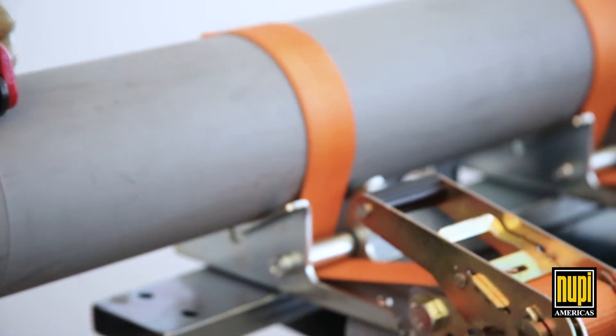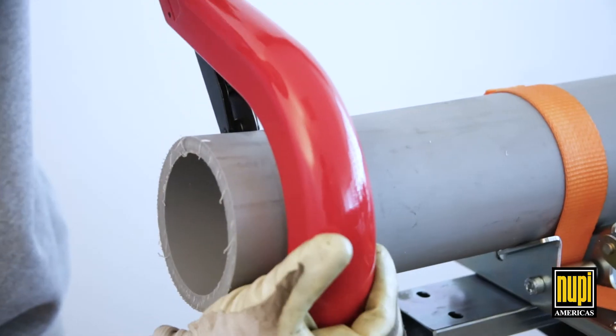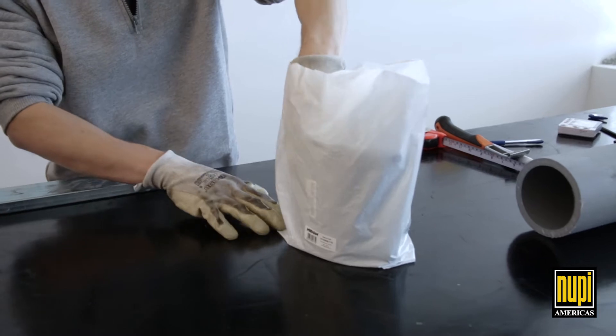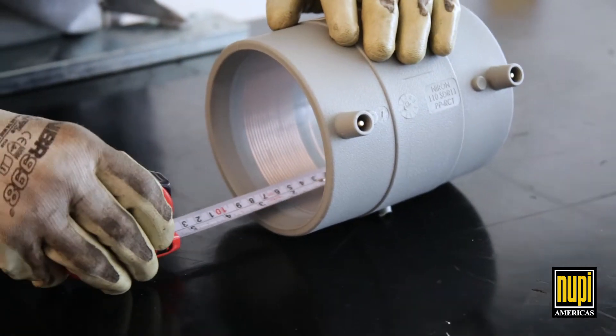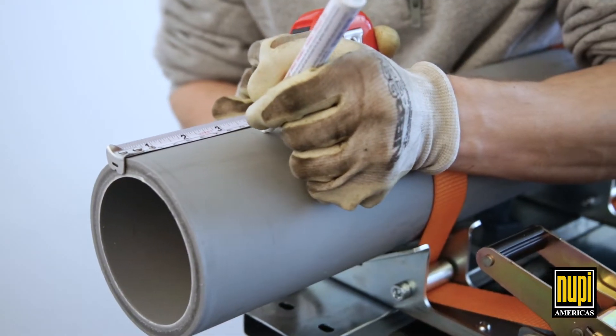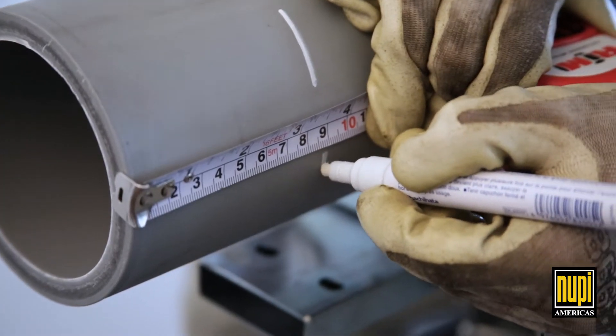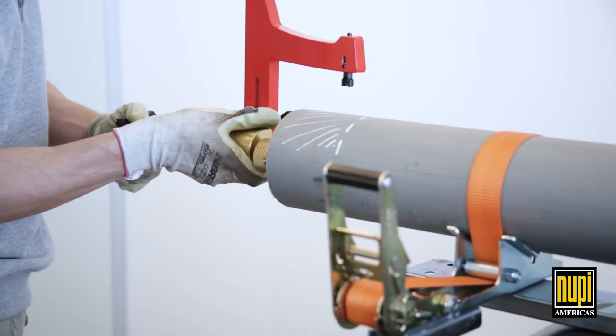Cut the pipes at right angles with a pipe cutter. Scrape the pipe and the fitting spigot surface uniformly to completely remove any oxidized layer. Scrape at least 3 eighths of an inch beyond the insertion length of the fitting.